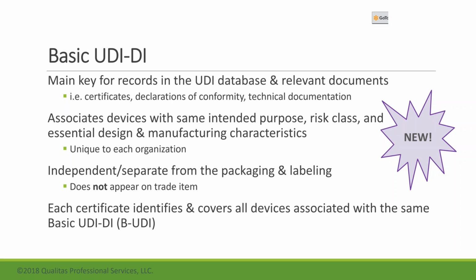So if any of you are familiar with the SRN, the single registration number, this is a requirement now of the MDR that every organization has this single registration number. Think of that as an author, okay? That's the medical device manufacturer, it's the author of a book. Now that book is going to be your basic UDI, okay?